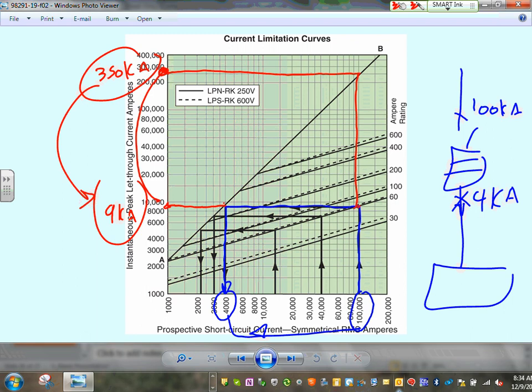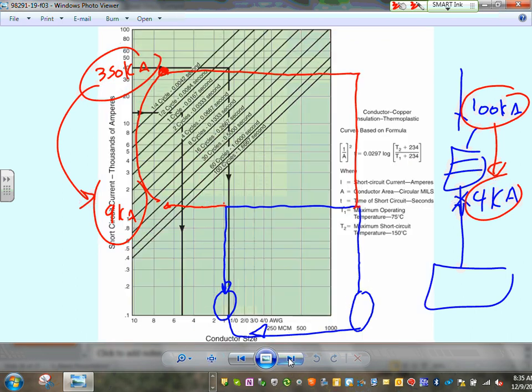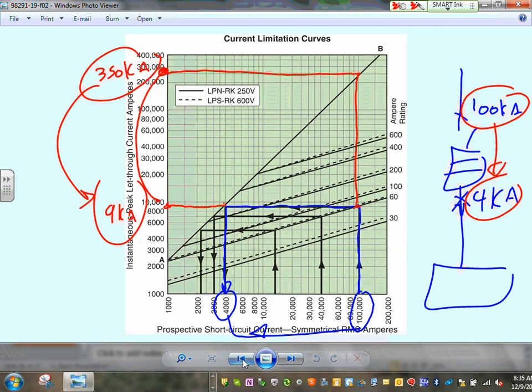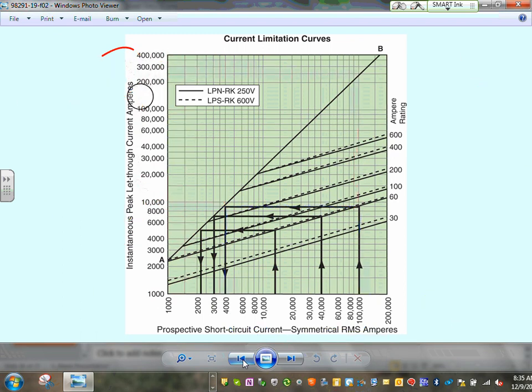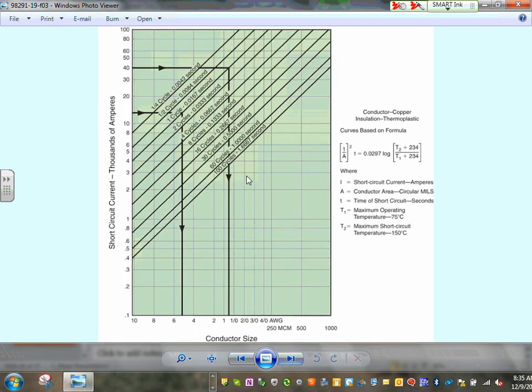That's all. So the smarter way, when you hear current limiting fuses, remember that it limits the current. It drops it down. How do they do that, guys? They open the fuse or circuit breaker so fast that it will basically limit your amount of energy. Any comments, guys? Any questions about the current limit fuses? We will talk about current limit fuses, guys, as we go into the industrial. You will hear a lot if you start in this industry too.